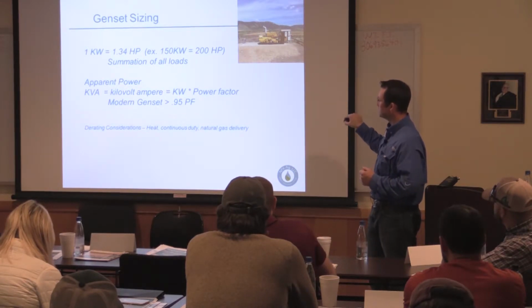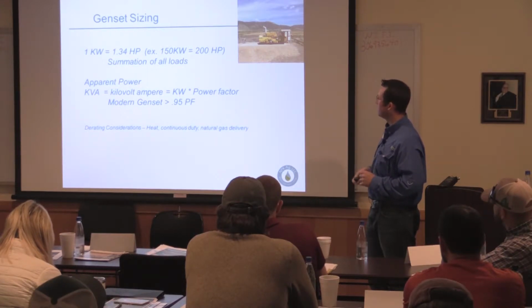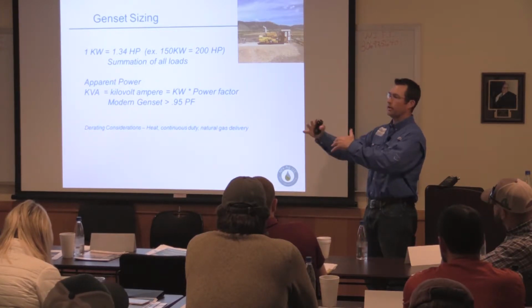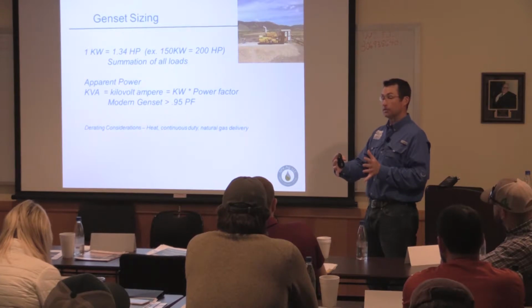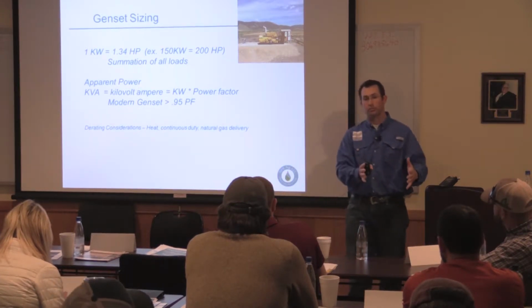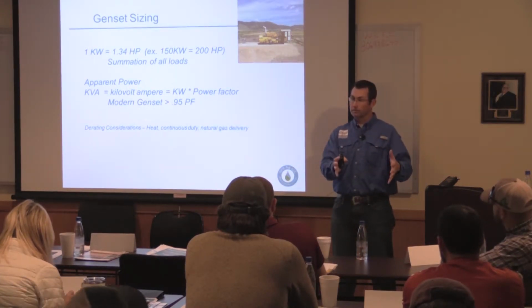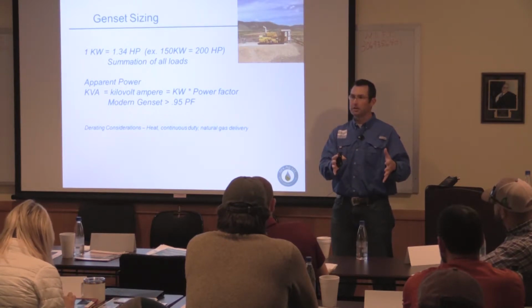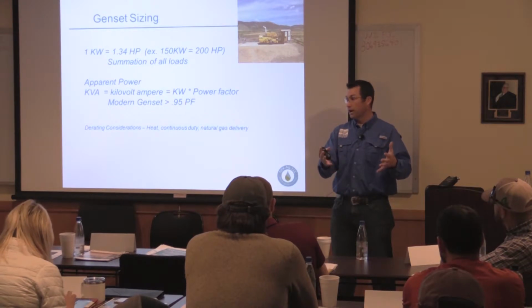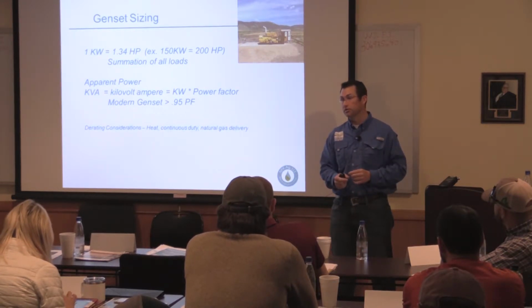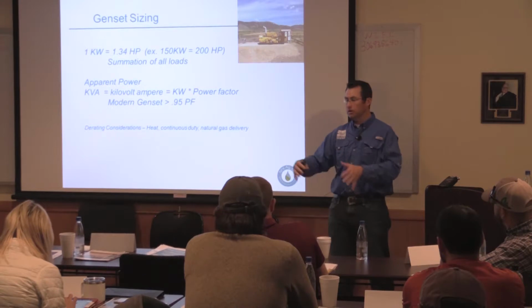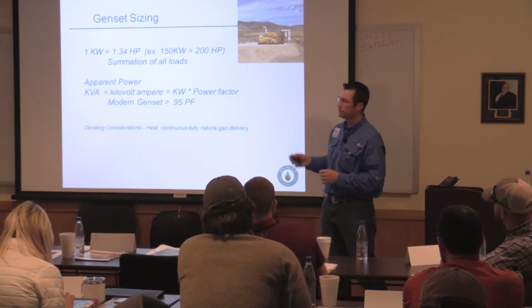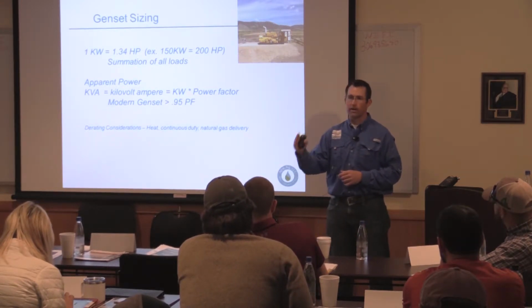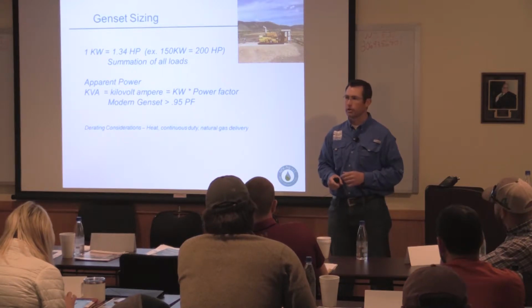So you're looking at a de-rate, meaning you need to oversize a little. The other thing is continuous duty. You want to make sure these are set up so they're not running all the way at max load, but at their continuous duty load. That's something you'll find in an industrial motor compared to an automotive style motor. Often with automotive style motors, we're pushing our luck running 454s, 350s, and 496s at high RPMs, well past their continuous duty cycle. With lower RPM cat-type motors, their horsepower rating is based on a continuous duty rating.